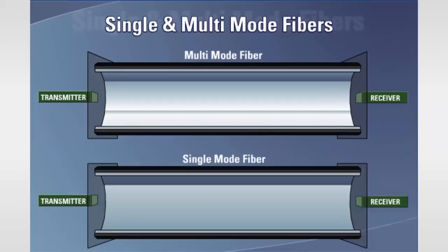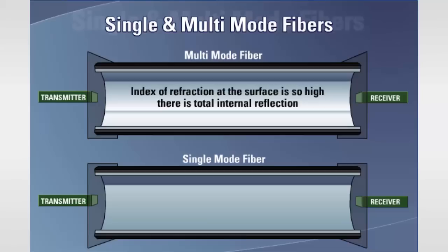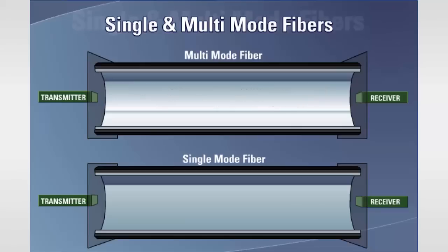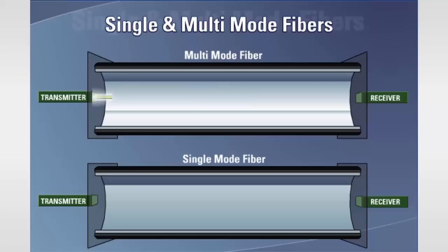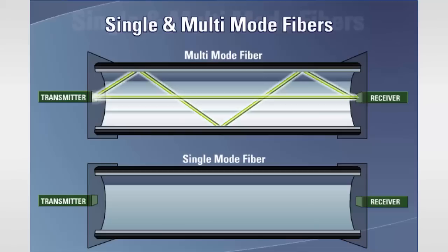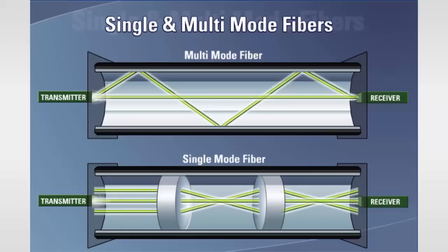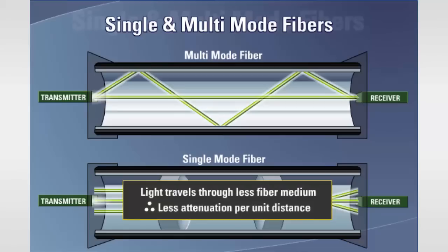There are two types of fiber optic cable in use today: multimode and single-mode fiber optic cable. Multimode fiber is constructed such that, for a given wavelength of light, the index of refraction at the surface is so high that there is total internal reflection — the fiber optic cable acts like a tube whose interior surface is polished like a mirror. Some of the light will travel straight down the tube, while some will reflect off the walls as it travels along. Single-mode fiber's construction is such that it acts as an elongated lens continuously focusing the light into the center of the fiber. Light traveling through single-mode fiber travels through far less fiber medium, resulting in far less attenuation per unit distance than light traveling through a multimode fiber.